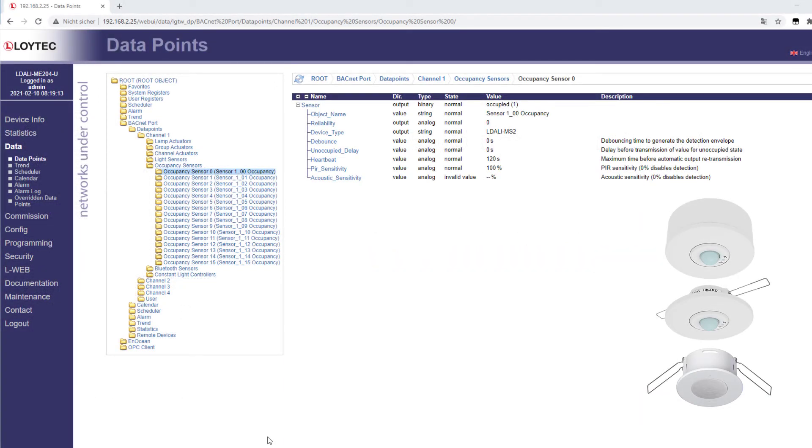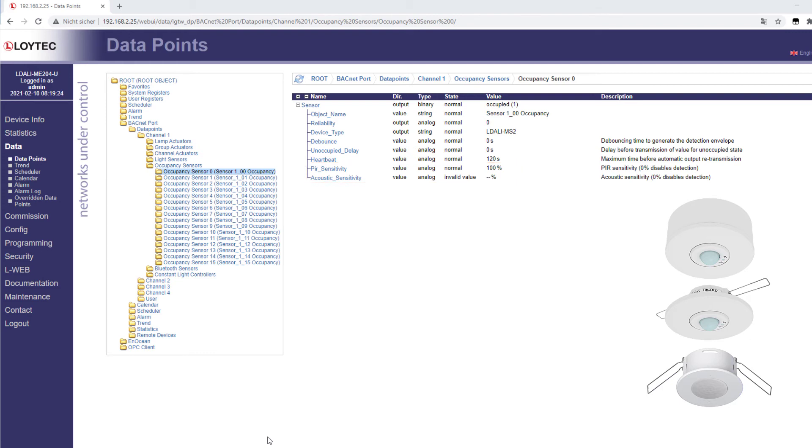For L-DALI modules with the BACnet interface, the data points PIR sensitivity and acoustic sensitivity have been added to the occupancy sensor objects. This enables easy sensitivity adjustments for different detection methods. The data point acoustic sensitivity only works for the L-DALI MS2BT and L-DALI MS4BT sensors, while PIR sensitivity can be used for any sensor that supports sensitivity according to IEC 62386-303.